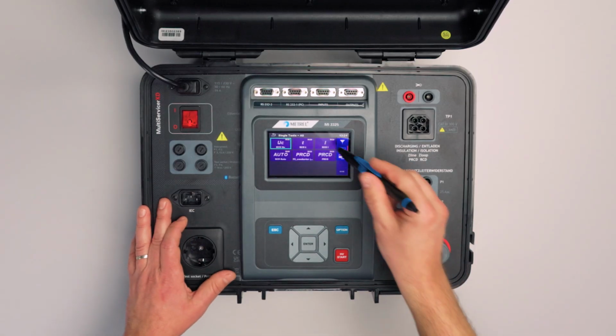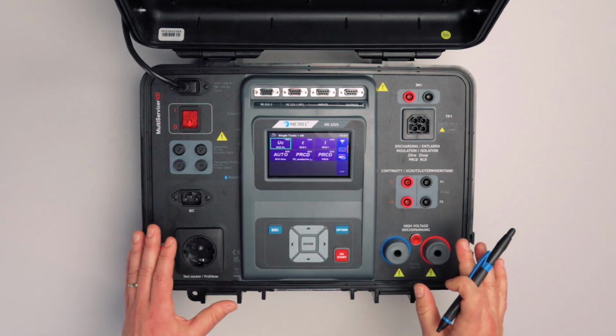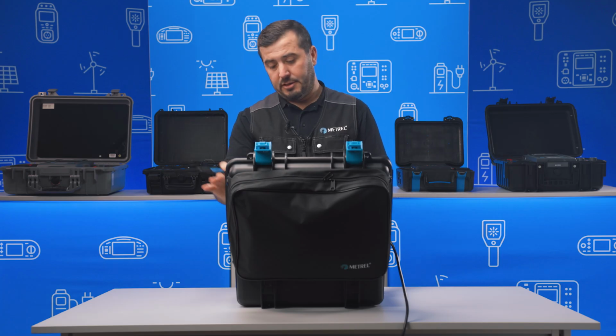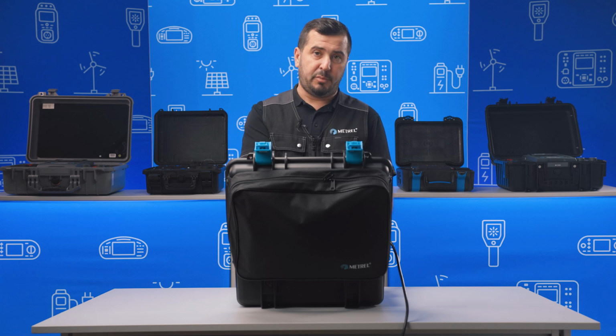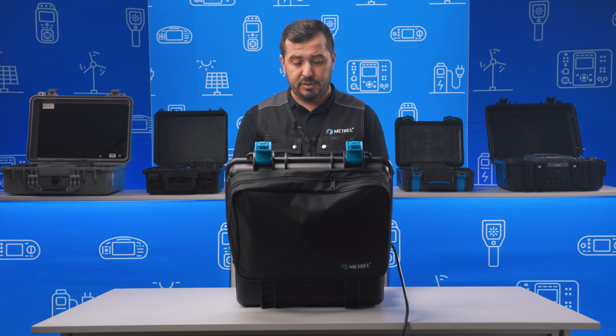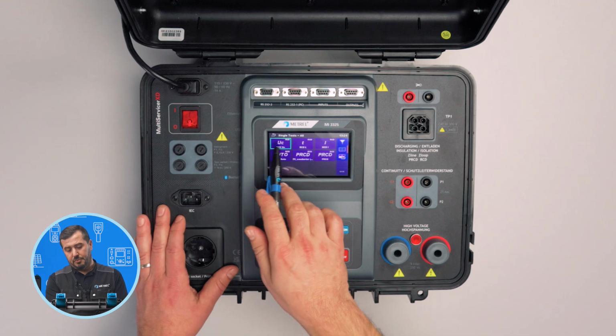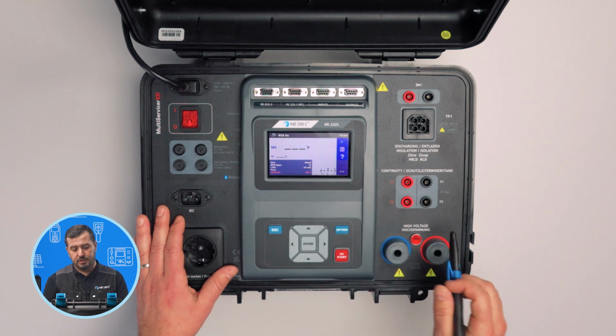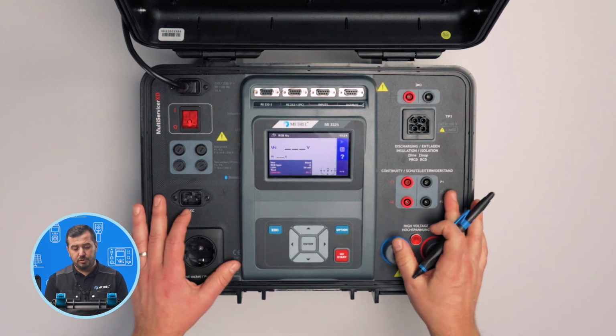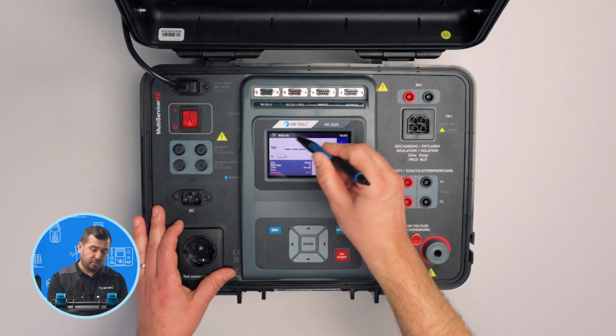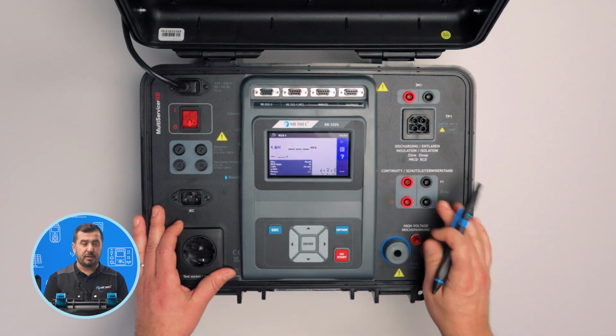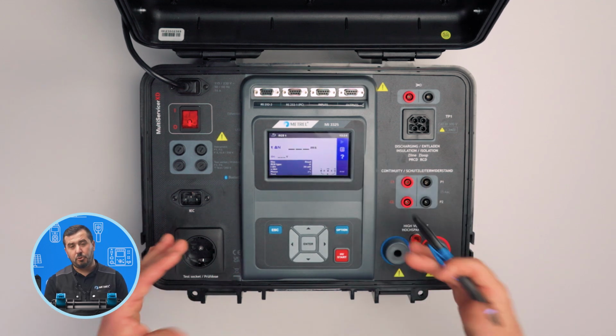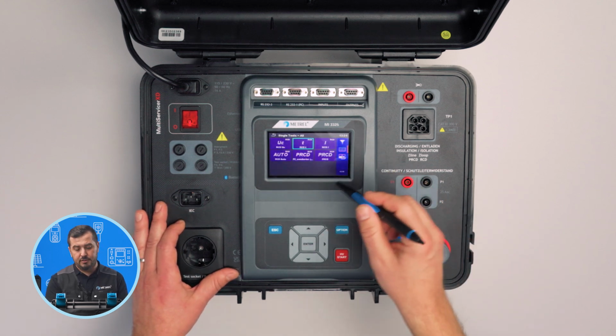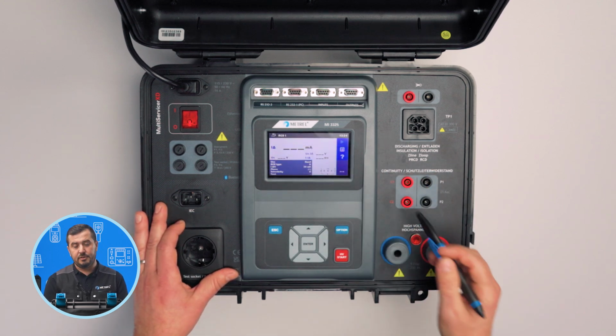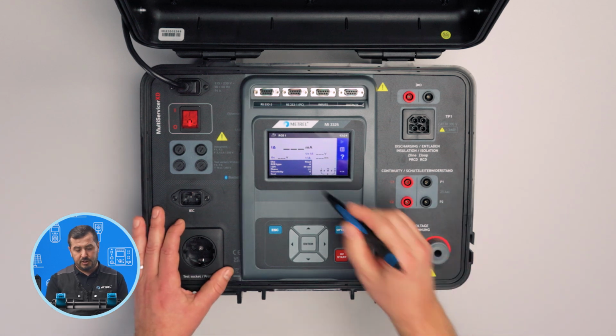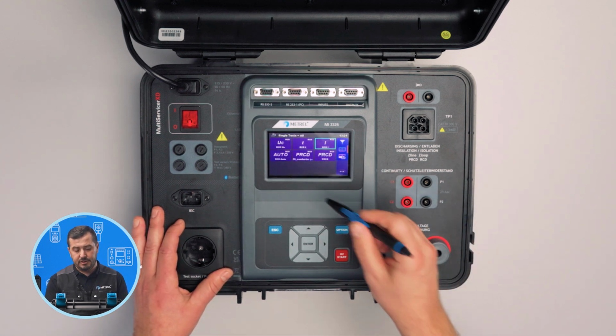RCD testing. This is also a group of the tests supported for the electrical installation safety part and for electrical equipment. So, for example, we can measure the contact voltage on the RCD. Then we can measure the trip out time of the RCD for different types. Then the trip out current of the RCD, again for different types.